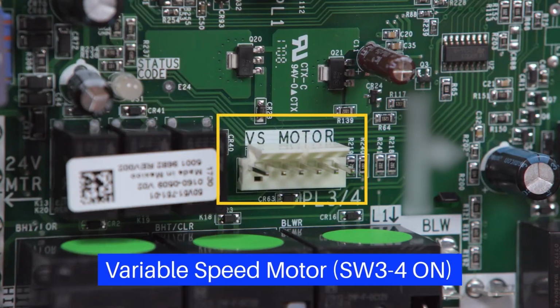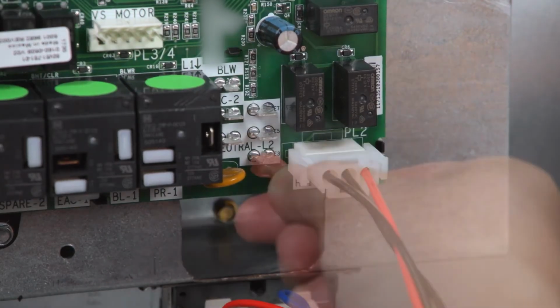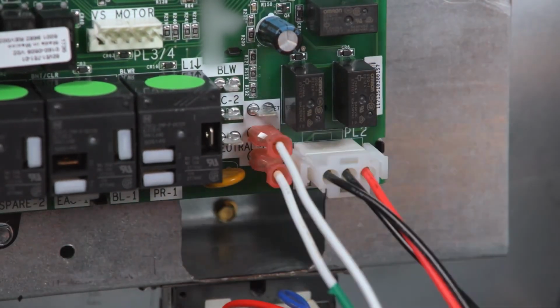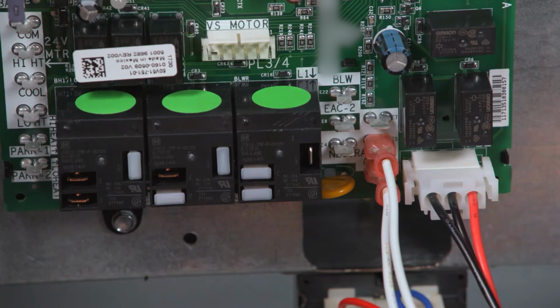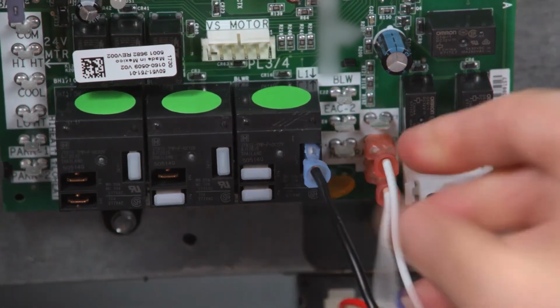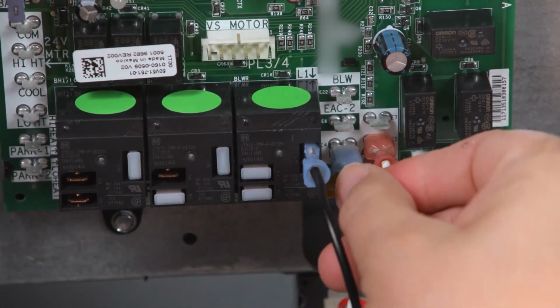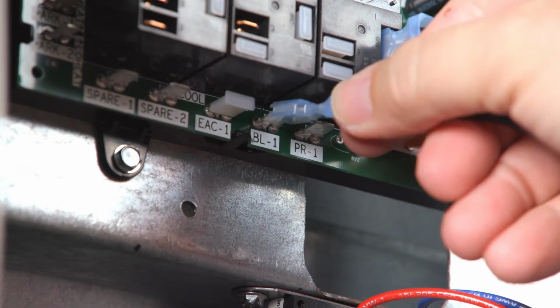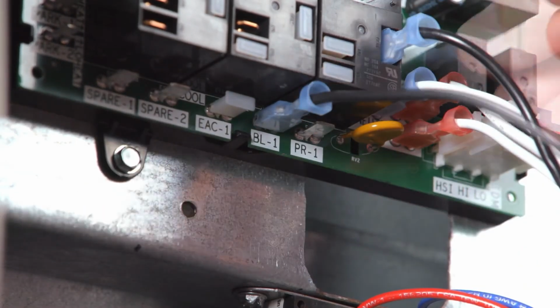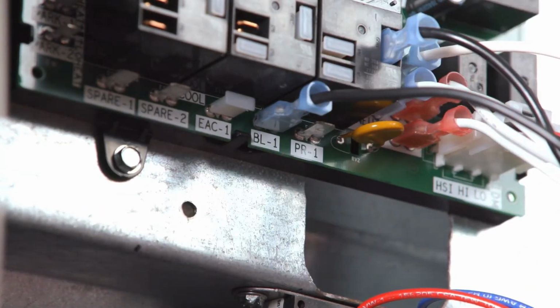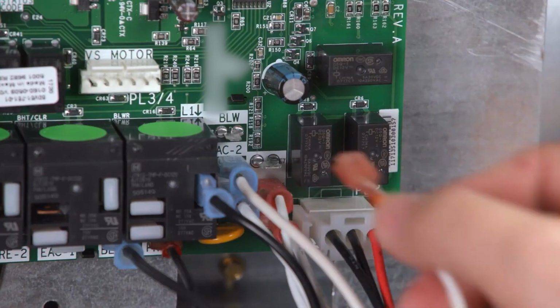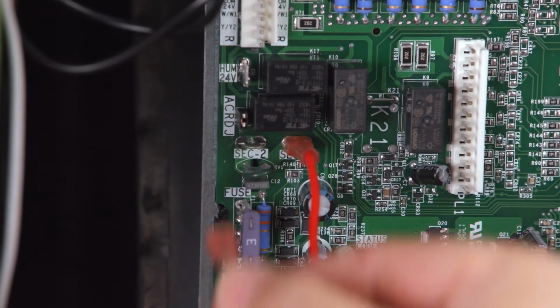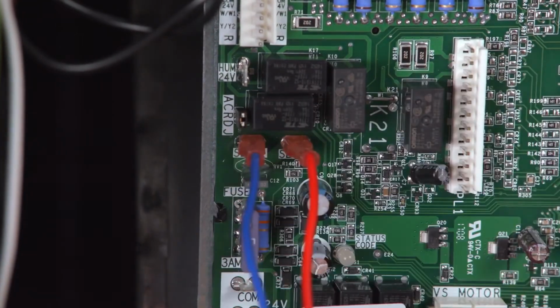When using a variable speed motor, plug the motor controller into the VS motor pins. Plug in the 3-pin Molex hot surface and inducer plug and neutral wires. Connect the 120-volt power to the L1 spade on the relay. Then connect the neutral wires. Connect the blower motor 120-volt power and neutral wires. Connect the 120-volt power and neutral transformer wires and connect the 24-volt power and common transformer wires.